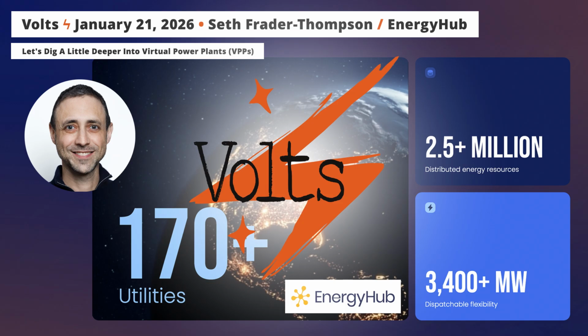What if you can just say, we're going to avoid setting a new peak demand, or we're going to avoid having the demand on this component last longer than a certain amount of time? So if you have a system that's looking across DERs and saying, okay, I've got this many cars behind this thing, this many air conditioners behind this piece of equipment, I'm looking at a forecast for how they're all going to come together, and I'm going to figure out which pieces of this demand puzzle I can shift to the right or to the left. You can bring that peak moment down, and you can avoid an upgrade. It's possible you could avoid that upgrade for, at the very least, a few years as table stakes, but ideally you're talking about avoiding that upgrade essentially forever, for the length of that component.